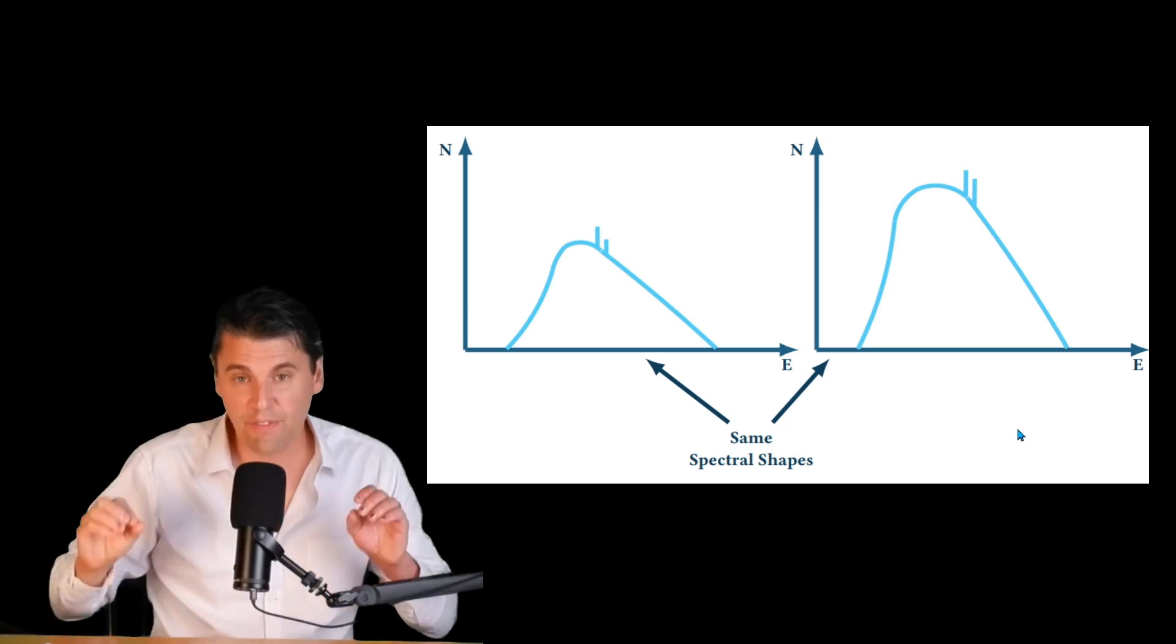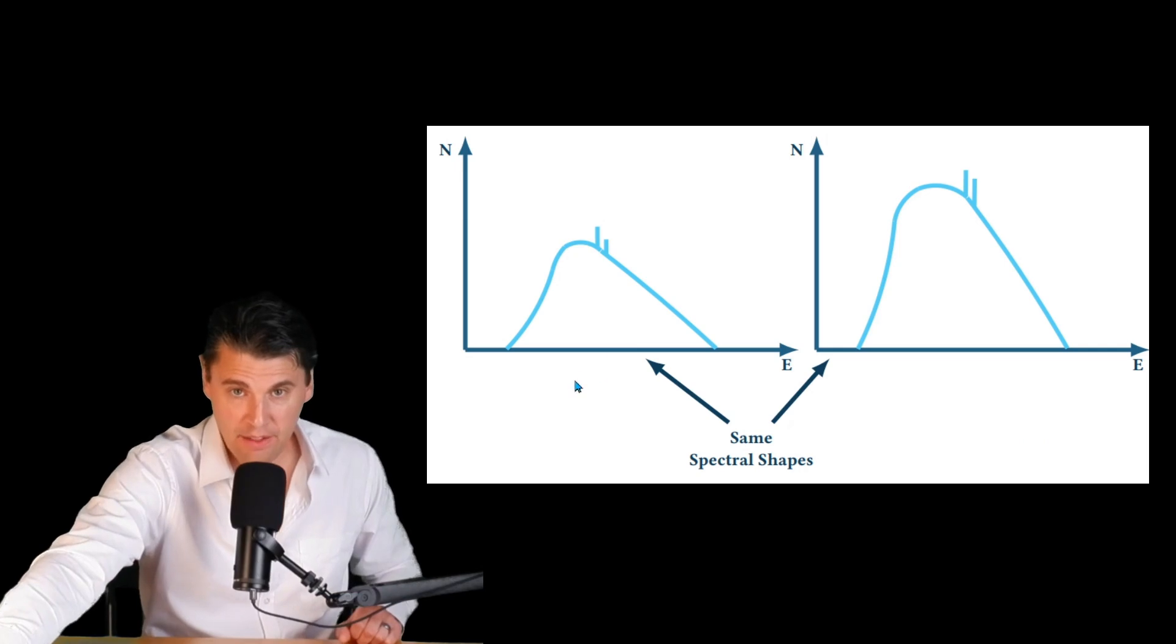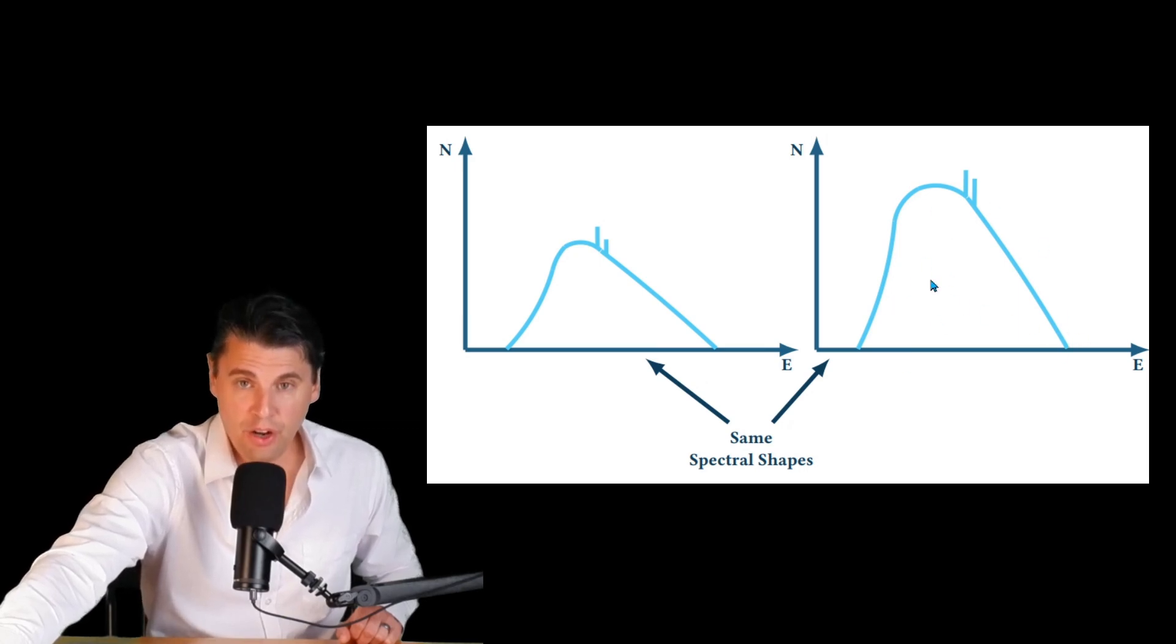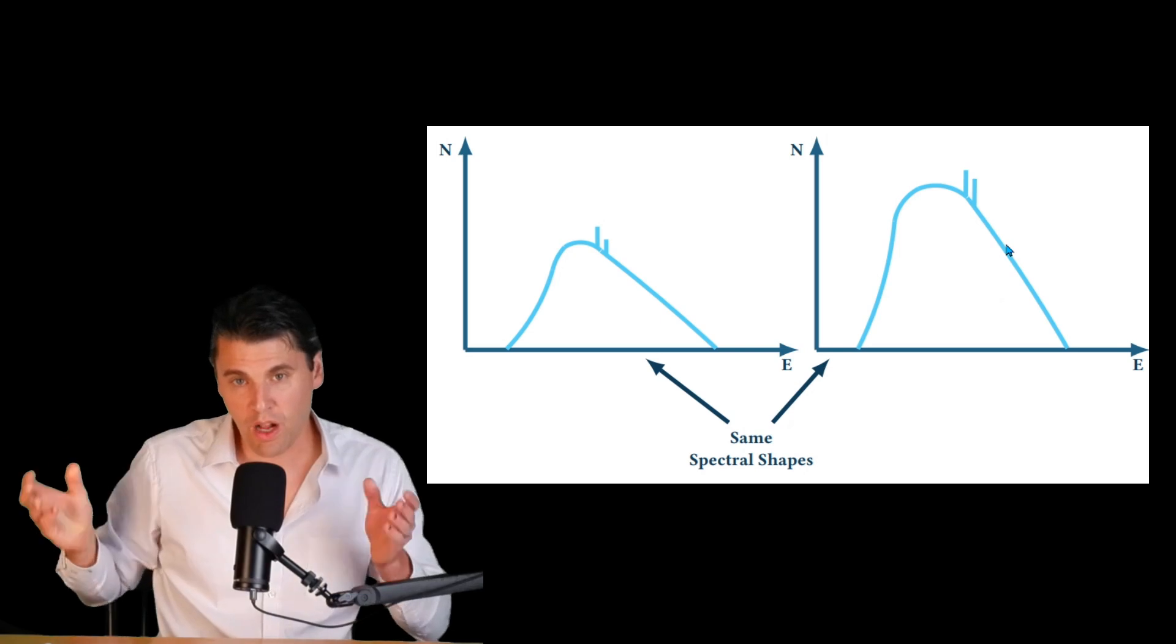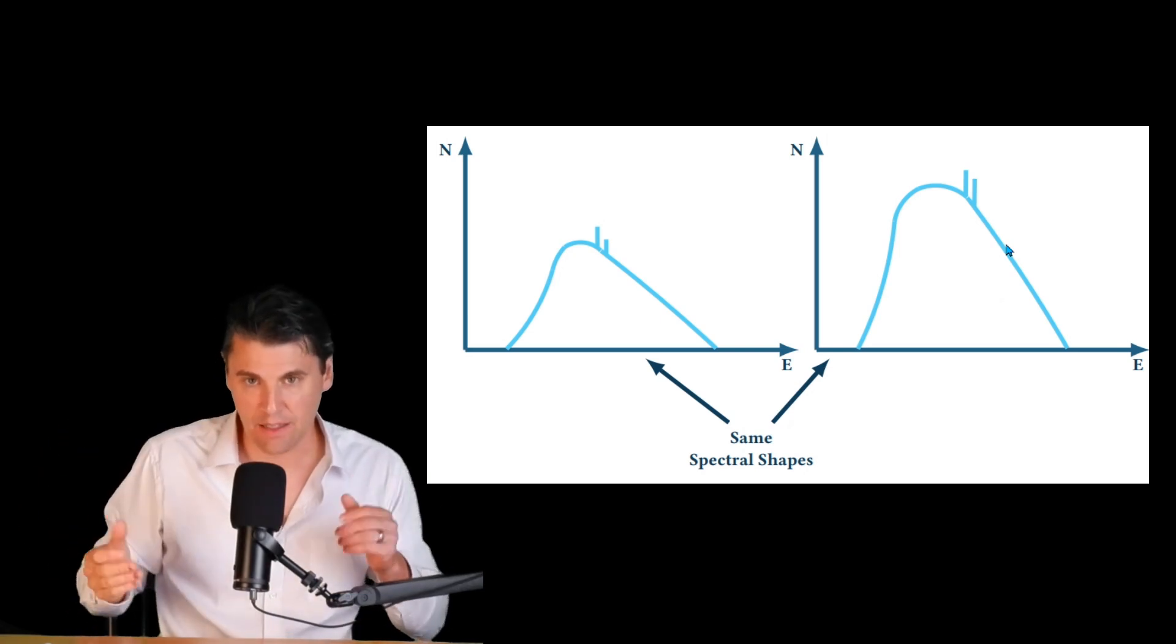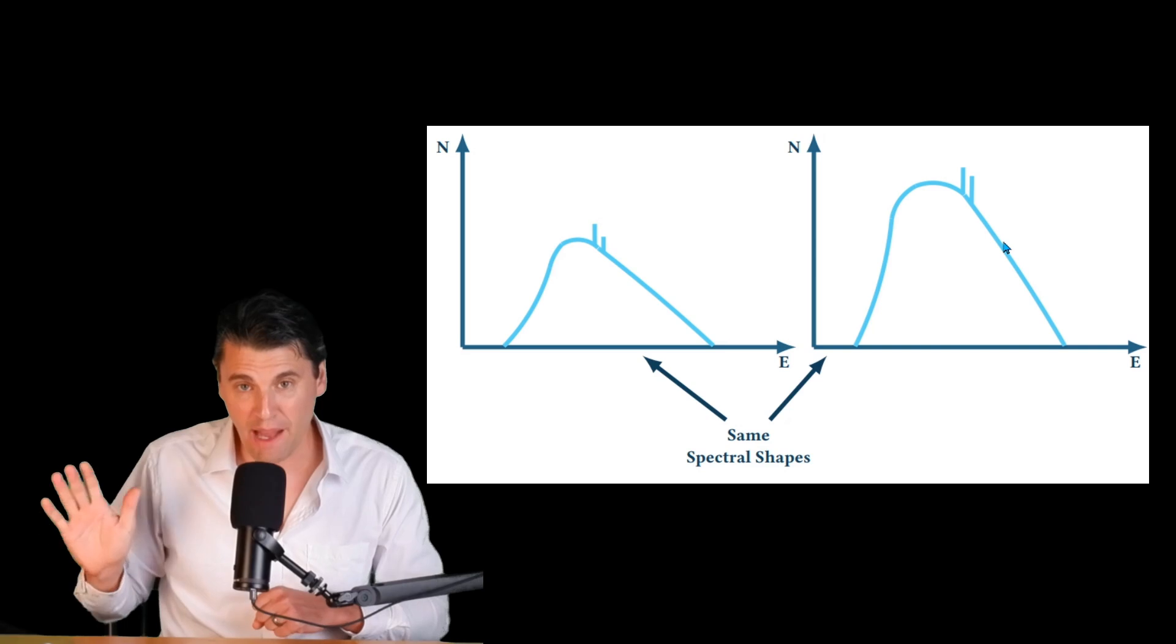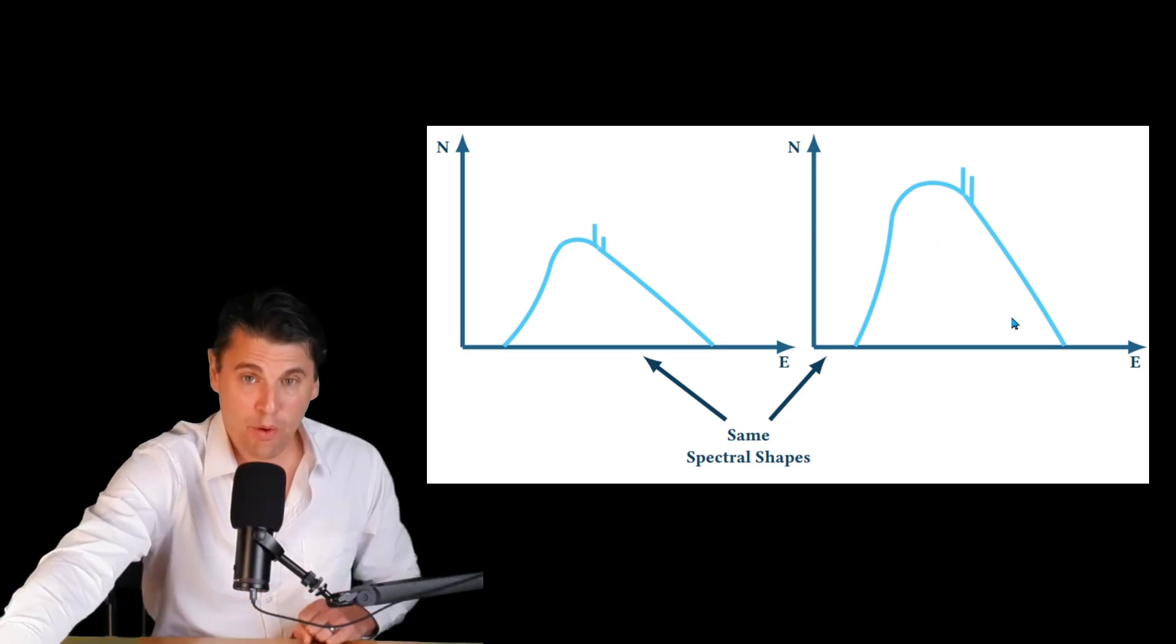On the other hand, if you had the same shape, but a different number of x-rays under the curve, the drawings aren't perfect here, but these are supposed to be the same shape, but a different number of x-rays under the curve. In this case, the number of x-rays we're calling quantity, we're only changing the beam quantity. If we change the tube current that we denote by the mA, that's going to change the beam quantity, but it will not change the shape of your x-ray spectra.